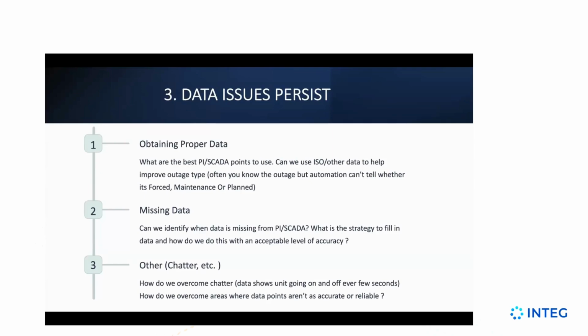Typically, when you're doing the automation, if you're missing 1 10-minute interval, there's nothing you can do. If in your auditing NERC comes back and says, hey, why did this happen? If you have a consistent strategy and you've documented what you're using, they're going to be fine. So just have a strategy that is defensible and use that strategy consistently for missing data.